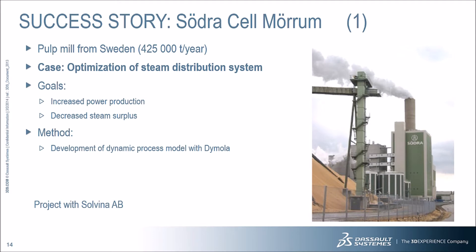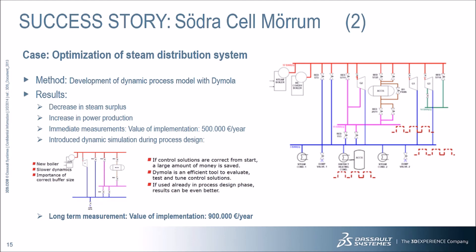A success story for the application of Dymola technology is Södra Cell Mörrum, a pulp mill in Sweden producing over 425,000 tons per year. This work with Solvina AB involved optimization of a steam distribution system with the goals of increasing power production and decreasing steam surplus. A dynamic process model was developed using Dymola to optimize the system. Analytic optimization highlighted critical areas for improvement, including a new boiler, slower dynamics, and the importance of a correct buffer size. The resulting decrease in steam surplus and increase in power production yielded an immediate value of €500,000 per year, and the long-term value has been measured at €900,000 per year.